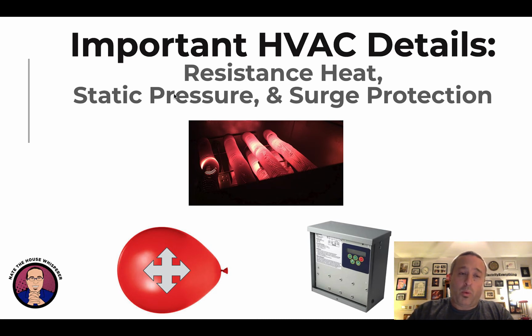What we're really going to focus on is called static pressure. This is the most important concept you've probably never heard of, and a lot of HVAC contractors aren't that familiar with it either. But it's utterly critical, because if you don't keep an eye on this, your system's going to be really noisy, and you're likely to have failures within one or two years after install. That's bad — you don't want to be replacing these fan motors. They're expensive. And there's all kinds of other things that go wrong with high static. You'll severely limit the life of your system with high static.